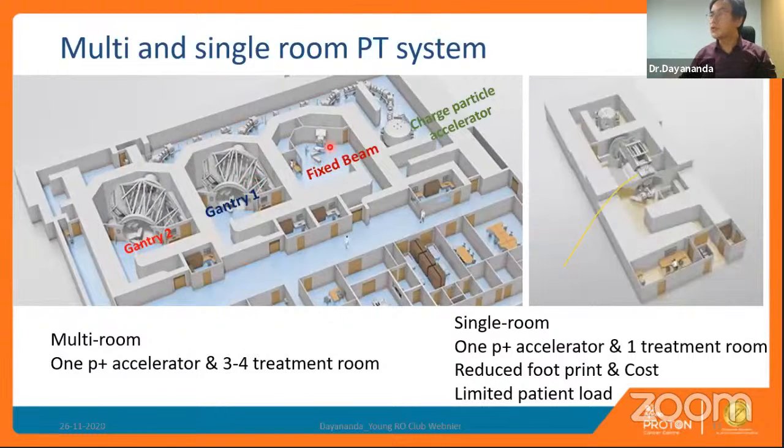But to make proton therapy available at a lesser cost, the industry has come up with a single-room solution, wherein you have a cyclotron and then a treatment room. You can see the footprint is reduced significantly, the construction cost is reduced significantly, the equipment costs are reduced significantly, and the maintenance becomes relatively simple. So this is a low-cost approach to make proton therapy available across the world.